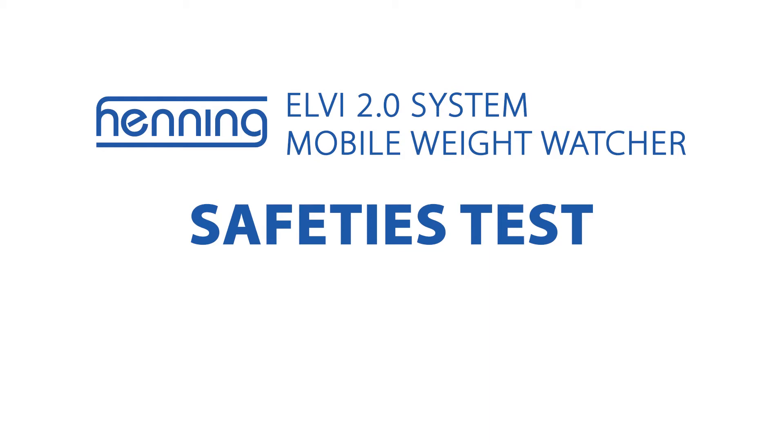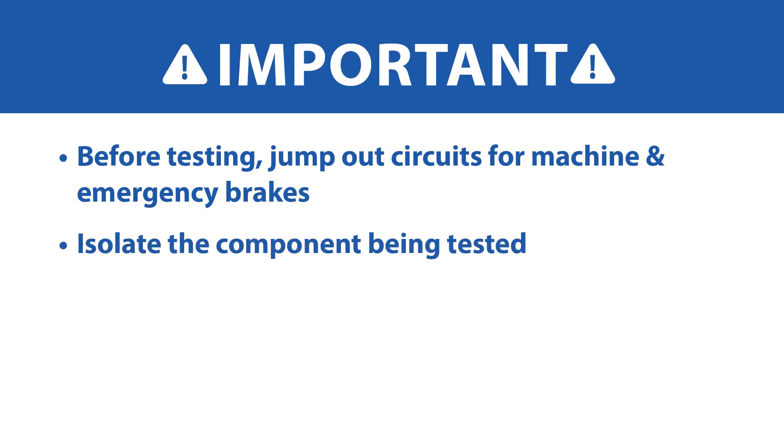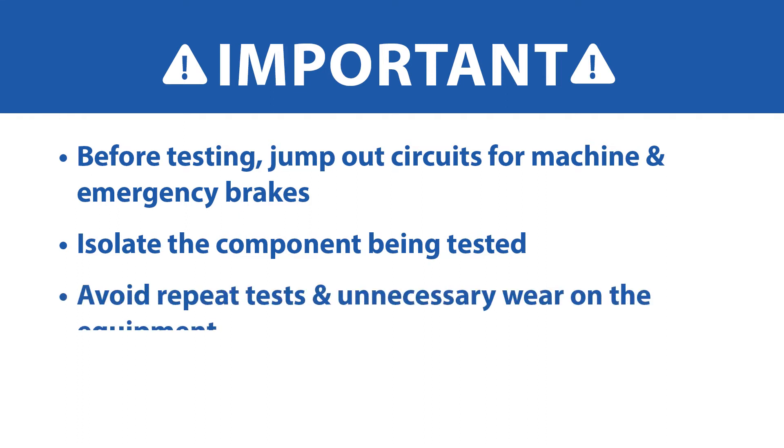This video describes how to conduct elevator safeties testing using the Henning ELVI 2.0 system from WurTech. When performing stopping force tests, it is critical that you know how to jump out circuits for machine and emergency brakes on the elevator controller to isolate the component being tested. Failing to do so will require you to repeat the tests to ensure accurate results.